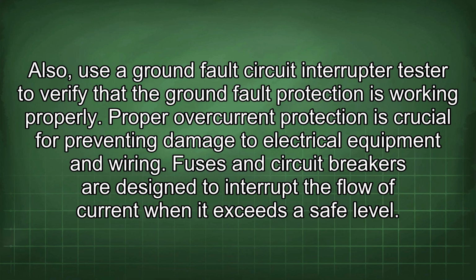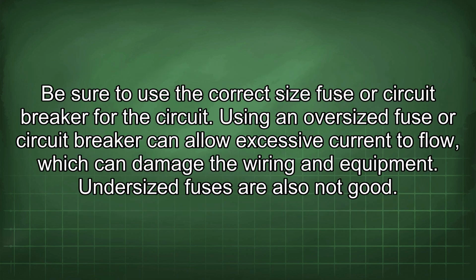Proper overcurrent protection is crucial for preventing damage to electrical equipment and wiring. Fuses and circuit breakers are designed to interrupt the flow of current when it exceeds a safe level. Be sure to use the correct size fuse or circuit breaker for the circuit. Using an oversized fuse or circuit breaker can allow excessive current to flow, which can damage the wiring and equipment. Undersized fuses are also not good.